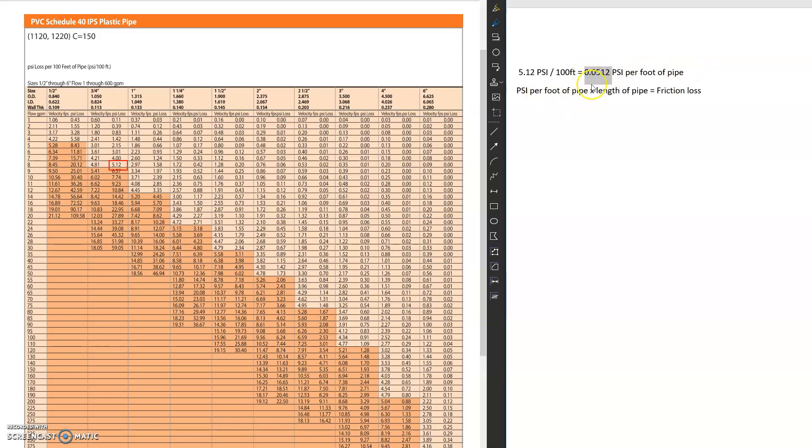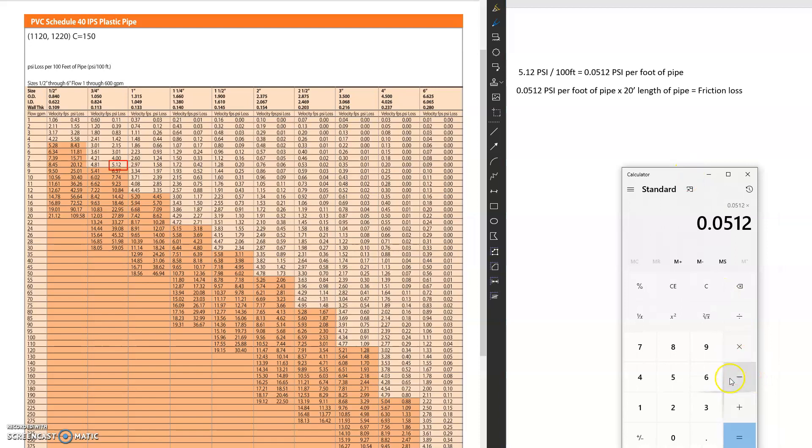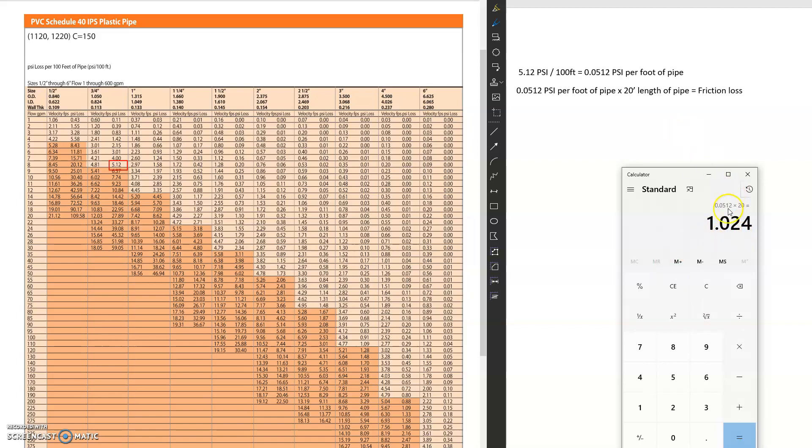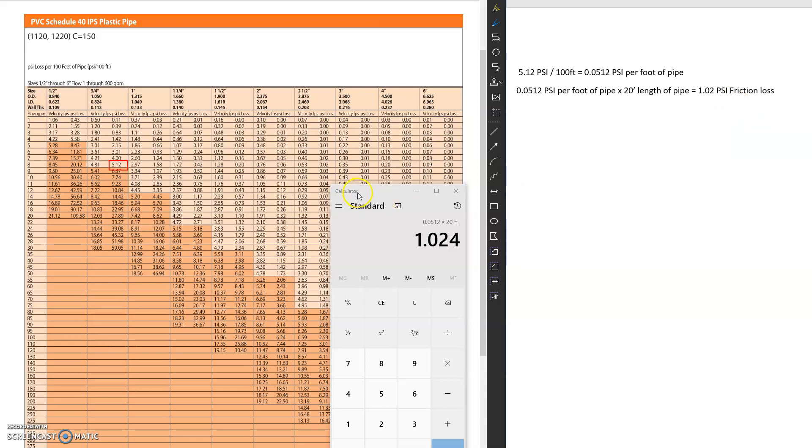So now we got our per foot of pipe here, and now we're going to multiply it by our length of pipe. So I said 20 feet. So then I'm going to multiply this by 20 feet. And you're going to see now our total friction loss for that pipe is going to equal 1.02 PSI for that 20 feet of pipe.